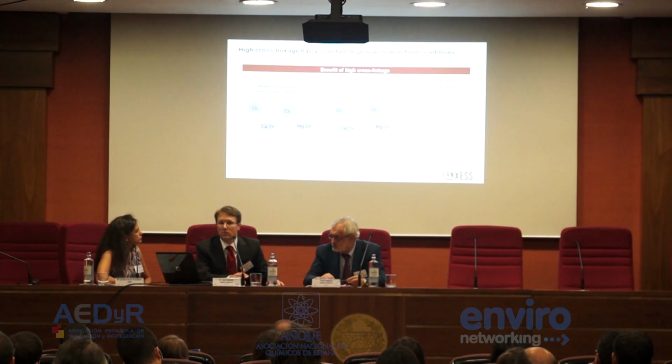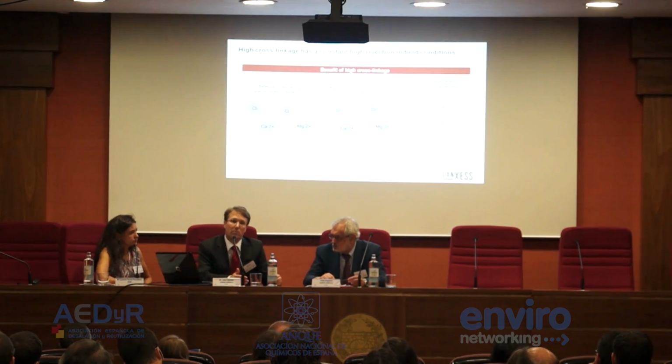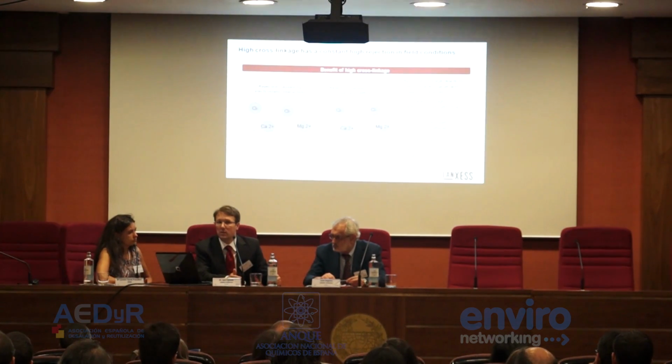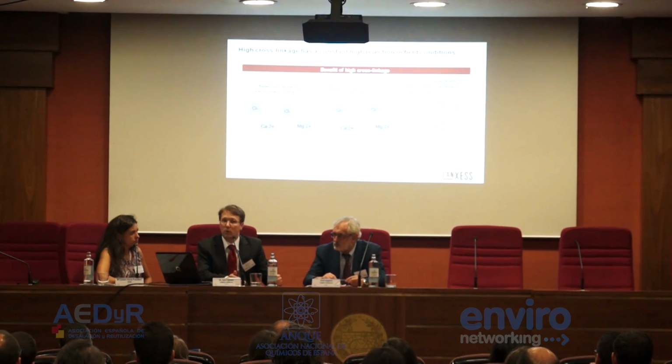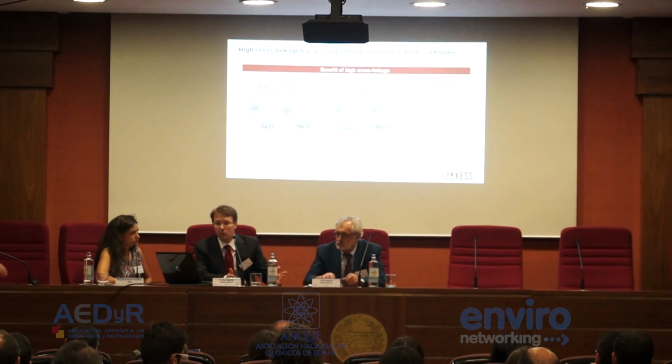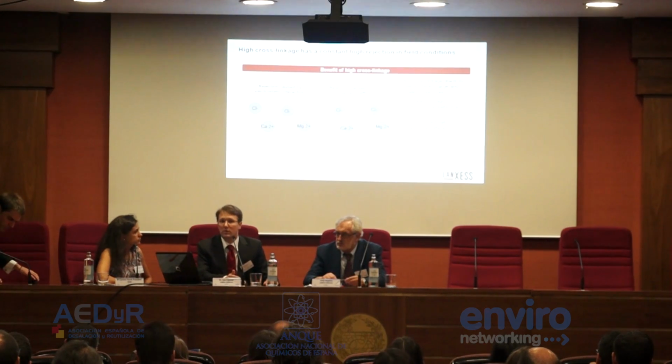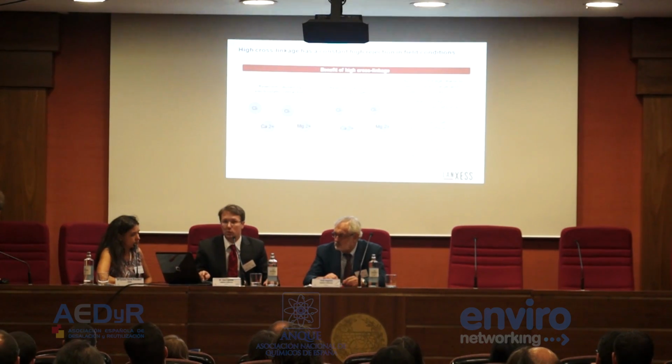You may also see it coming up more and more that some producers of RO membranes are adding more than just the sodium chloride rejection to the datasheet. This simply shows you that it is a good membrane if you give more information about boric acid rejection, nitrate rejection, and silica rejection. And since these components are critical, we check them in the laboratory.